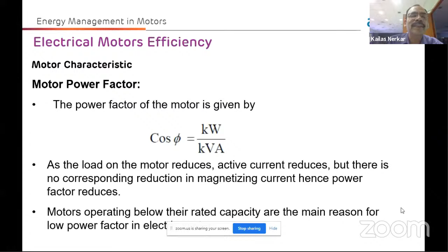As the load on the motor reduces, the active current reduces, but there is no corresponding reduction in magnetizing current, hence the power factor reduces. The power factor reduction in an induction motor is very high. Normally all induction motors have lagging power factors. So for that lagging load, power factor correction is required. You can put in a capacitor and correct the power factor. Similarly, motors operating below their rated capacity are the main reason for low power factor in an electrical system, because some of the motors are of high capacity but operate at low load. At that time also their power factor is very low.